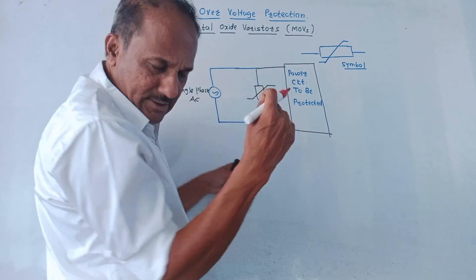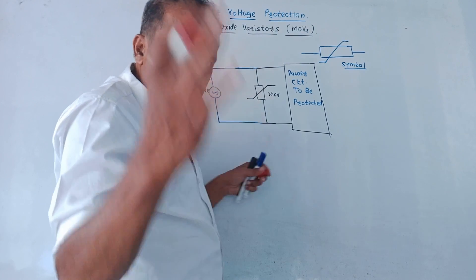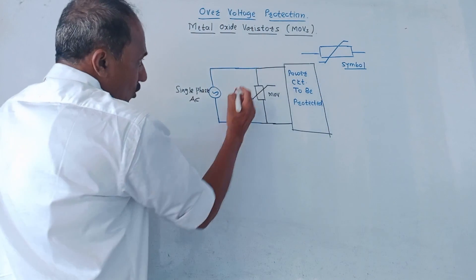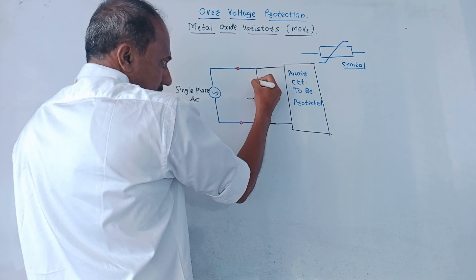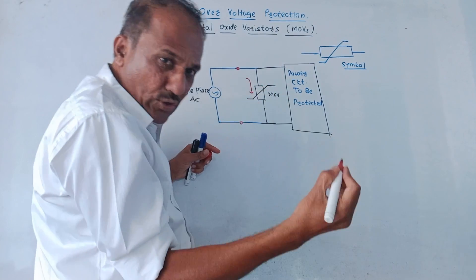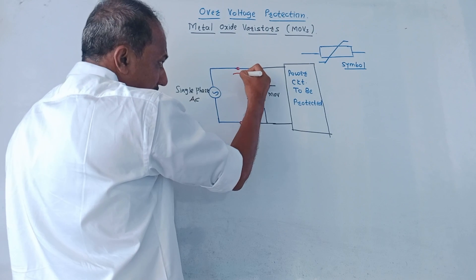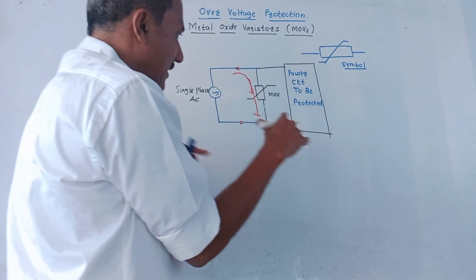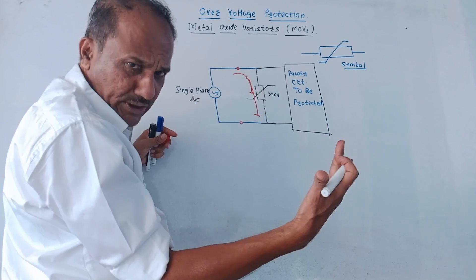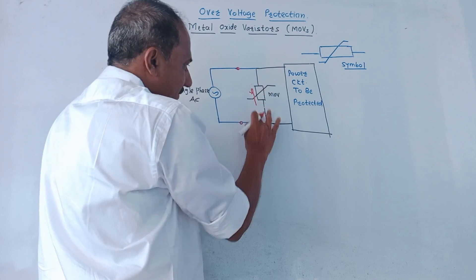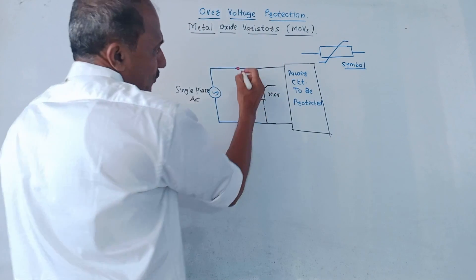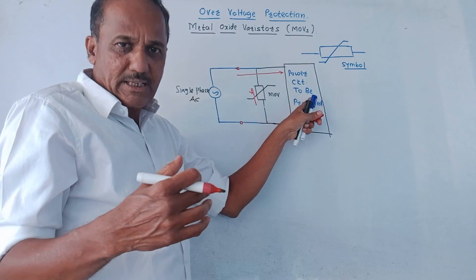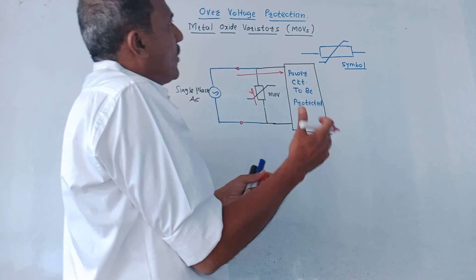Whenever there is a voltage spike from the input side, this device produces very low impedance, ideally zero resistance, because of which any voltage spike will pass through this device and will not pass through the power circuit, and the circuit will be protected. On the contrary, if there is normal operating voltage — not a voltage spike — then this device offers normal high resistance or high impedance, because of which the normal voltage will be passed to the device under consideration. This is the simple technique which provides overvoltage protection.